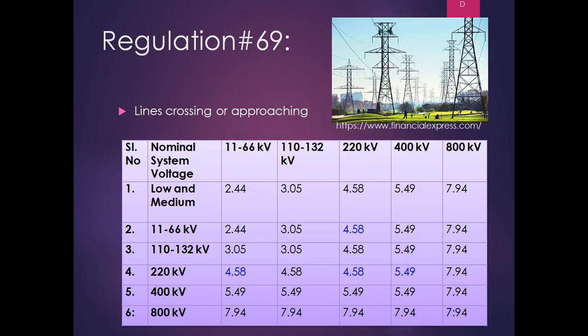Regulation 69 covers clearance between two conductors of different system voltages or different circuits. A simple table is provided. For example, if one tower carries 220 kV and another carries 400 kV, the distance between the two nearest conductors at the intersection point shall be 5.49 meter. Similarly, for 66 kV and 400 kV the clearance is again 5.49 meter.